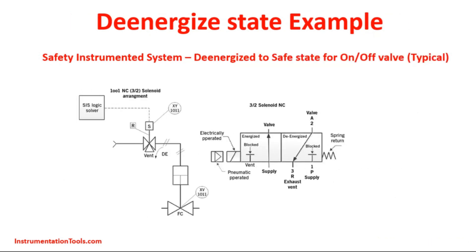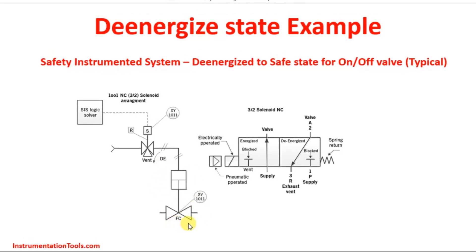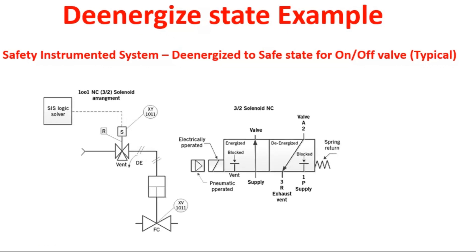We are going to see the detailed example briefed in the earlier slide. This is a SIS valve — a safety instrumented system valve — it is an on-off valve. FC stands for fail-closed position: whenever there is no air or no power, the valve goes to the closed position. The valve is being operated through a SIS logic solver, which gives the electrical power output to the solenoid valve to open and close.